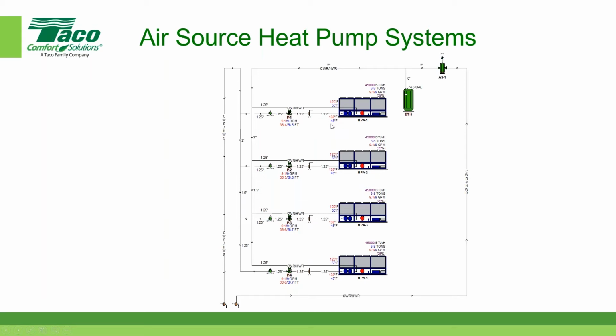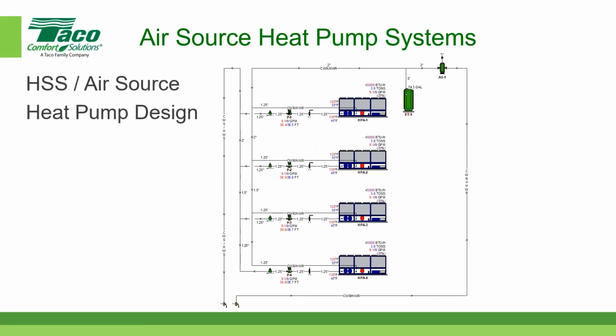And I've set this up as a primary variable flow. So I have the circulators, and I've got these 2 valves here showing where it connects to the rest of the system. I broke it up into 2 pictures so it'd be easier to read. If I had the whole thing on one page, it becomes very tiny and difficult to look at. So then it goes out. There's the air source heat pump design, outside components.